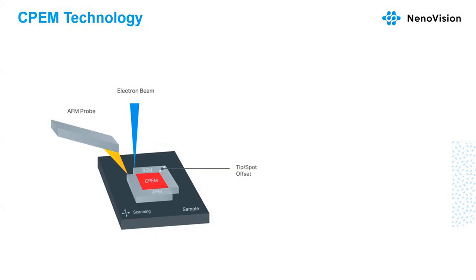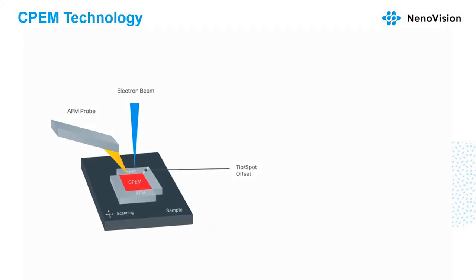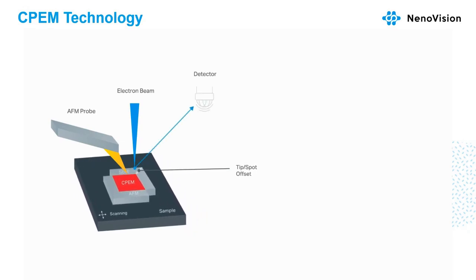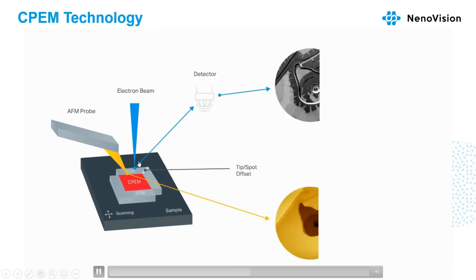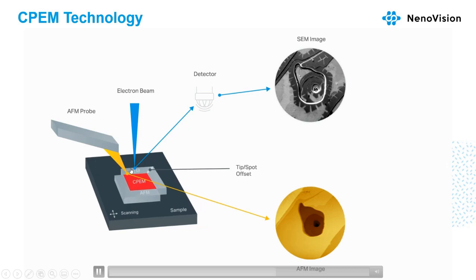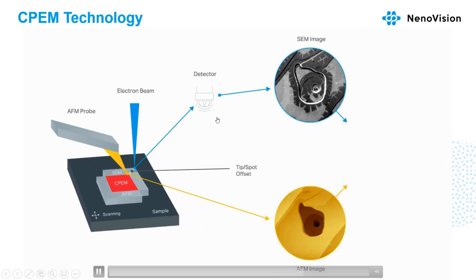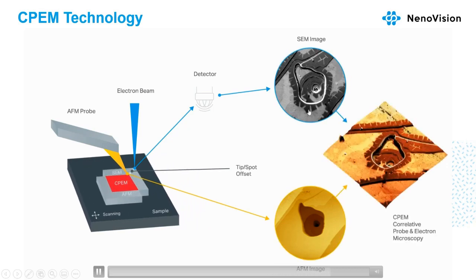And so, as this technology is the most important one to understand, I have another scheme here one more time, where we have the AFM probe and the electron beam, which point very close to each other. There is a slight offset, and we are measuring the sample. We get at the same time the data from SEM and the data from AFM. And so this way we correlate them into one three-dimensional image.